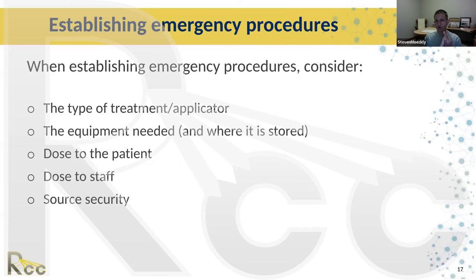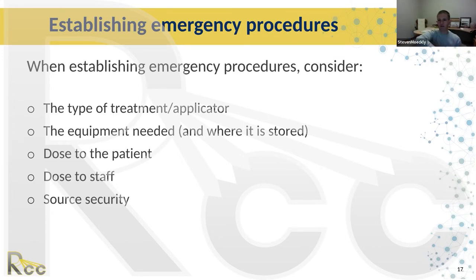The easiest applicator to remove would be a vaginal cylinder; an endometrial applicator might be more difficult. You need to think about your response in different situations. Consider the equipment needed, where it's stored, and where you'll place it in the room. The pig should generally be on wheels and positioned so that when the doctor removes the applicator from the patient in an emergency, they can put it directly into the pig without having to reposition it — every second counts.